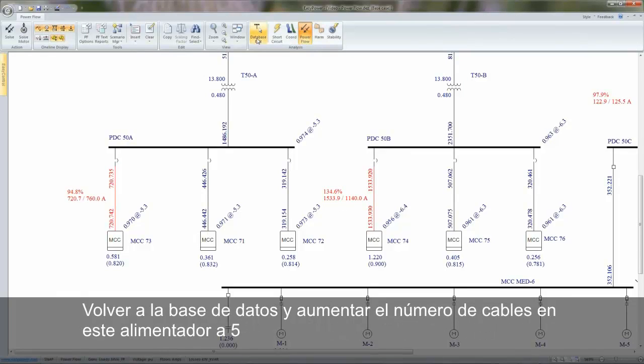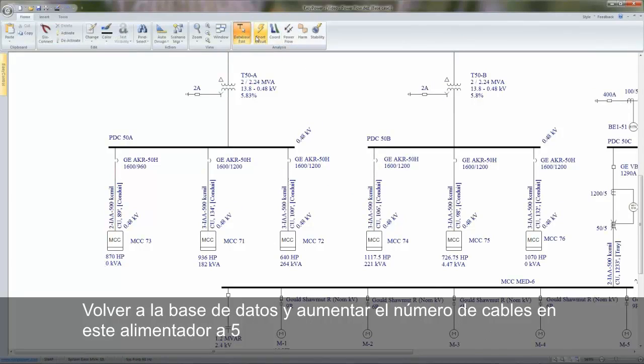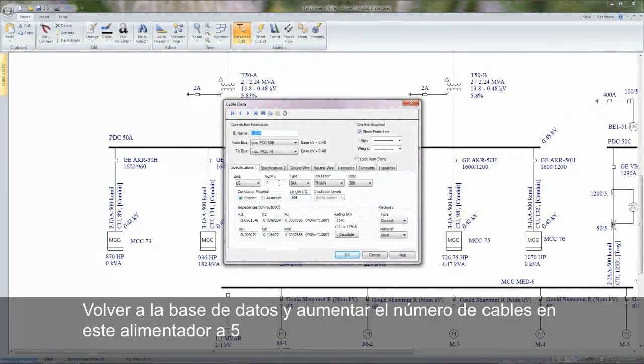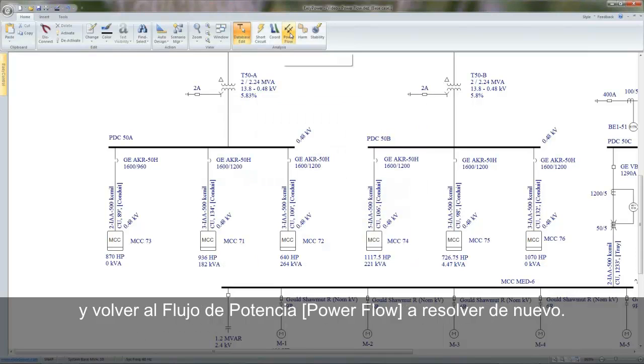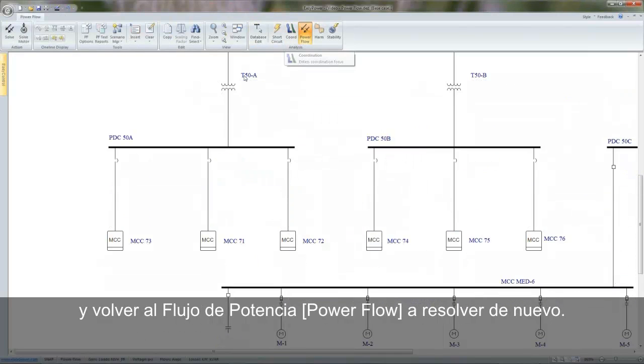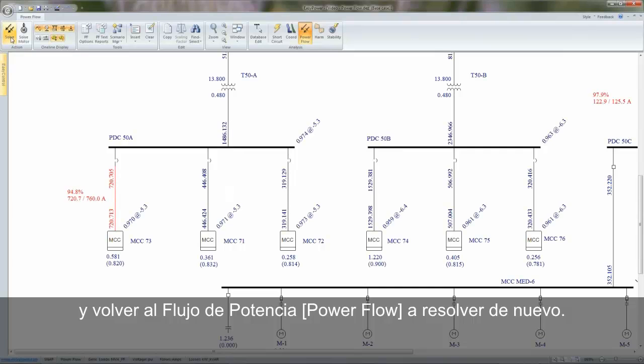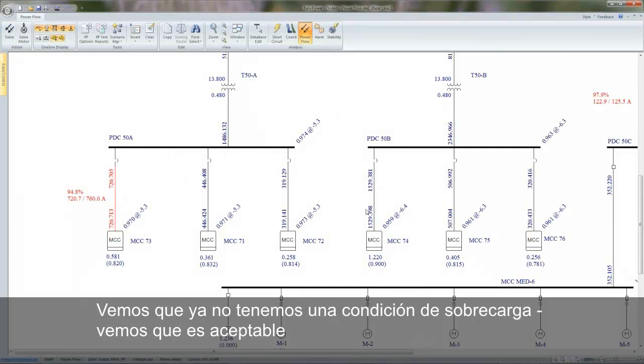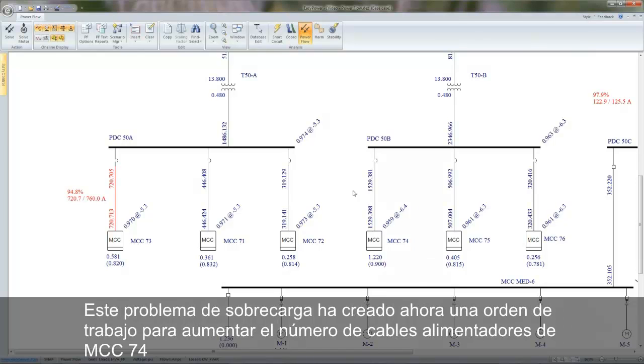Now if we go back to the database and we increase the number of cables on this feeder to 5 and go back into power flow and solve, we see that we no longer have an overloaded condition. We see that it's acceptable. This overload issue has now created a work order to increase the number of cables feeding MCC 74.